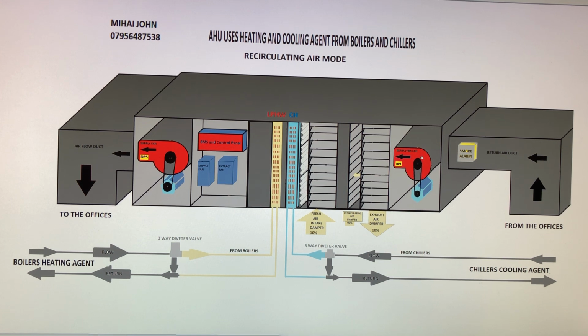When you start the fan, the dampers are just 10% open. The fresh air intake is 10% open. I'm taking only 10% because I don't want to lose the temperature from within the store. And the exhaust air damper pushes out 10%. I'm recirculating 90% of the air of the store. I just use 10% because I want to overcome the carbon dioxide problem. So I'm recirculating the air through the store. It's quite easy, so the air is recirculated through the store.